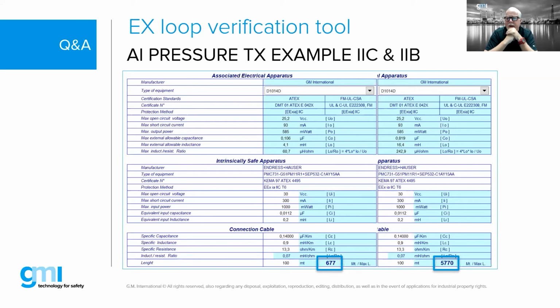And the reasoning for that is that we actually have more stored energy the longer the length of cable, if you will. Now we have increased storage capacitance and inductance with the cables. So depending on the gas groups, depending on the curves, we could have variations. We always have to make sure that we take that into account. Yeah, we have to verify what area we're looking at, the area classification and the gas group, because different gas groups have different maximum energy that you can transfer.